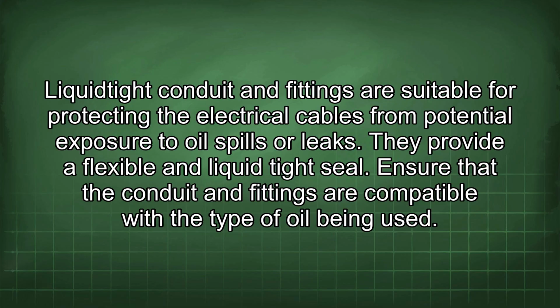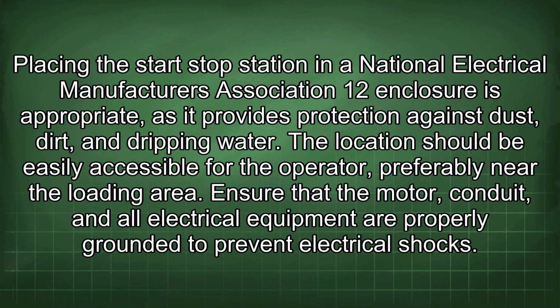Ensure that the conduit and fittings are compatible with the type of oil being used. Placing the start-stop station in a National Electrical Manufacturers Association 12 enclosure is appropriate, as it provides protection against dust, dirt, and dripping water. The location should be easily accessible for the operator, preferably near the loading area. Ensure that the motor, conduit, and all electrical equipment are properly grounded to prevent electrical shocks.